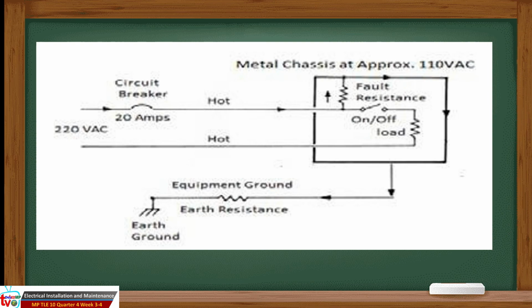The next figure depicts the same appliance with an equipment grounding conductor connected to the metal chassis. The equipment grounding conductor provides a low resistance path for the fault current. If the equipment grounding conductor is 100 feet of copper wire, size number 12 American wire gauge, then it has a resistance of less than 0.2 ohms. If the fault resistance is less than 5.3 ohms, then more than 20 amperes of fault current will flow in the circuit. The circuit breaker will trip off and de-energize the circuit.